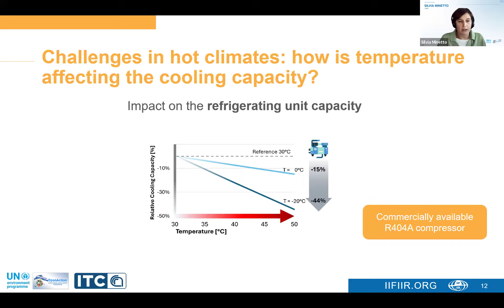So what happens if we combine these two challenges? On one side, we have an increased thermal load. On the other side, we have a decreased cooling capacity of the unit. What happens is that, for example, when we have to pull down the air again to the set point after door opening, the system has to work longer with respect to the reference situation. On the left hand, we have the situation in the desertic climate. So there is an increase in the pull down time, which can be around 100%. It means that it takes double the time to pull down again the internal air volume with respect to the design point.